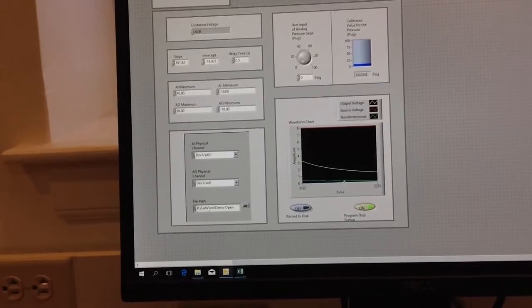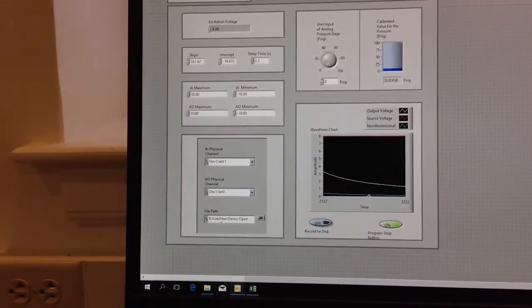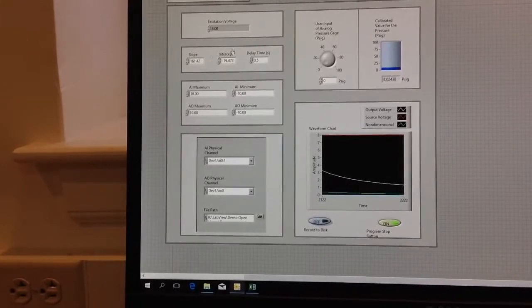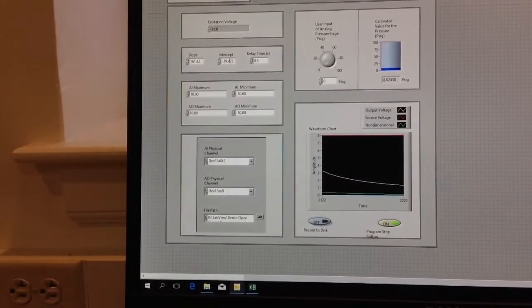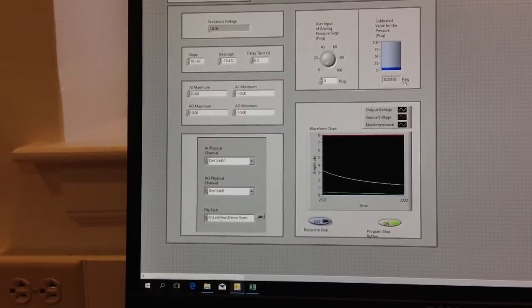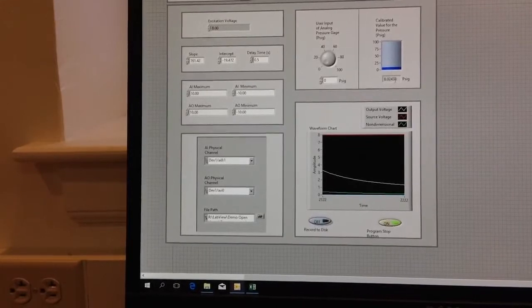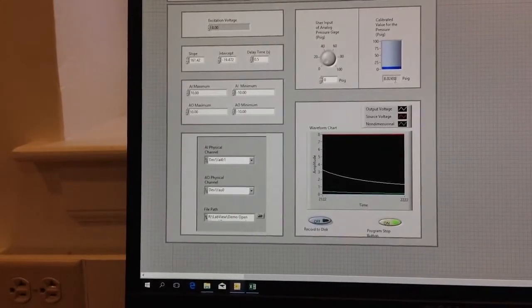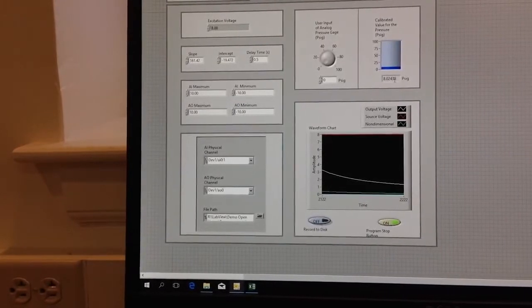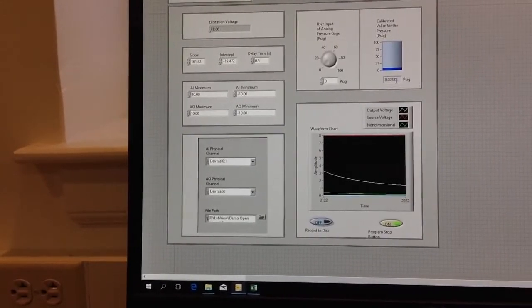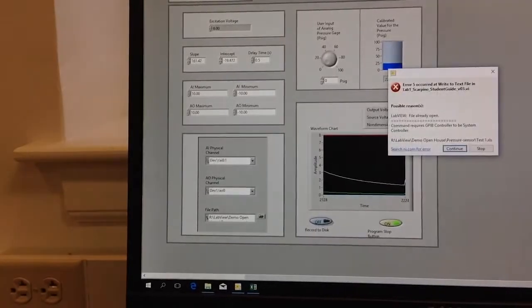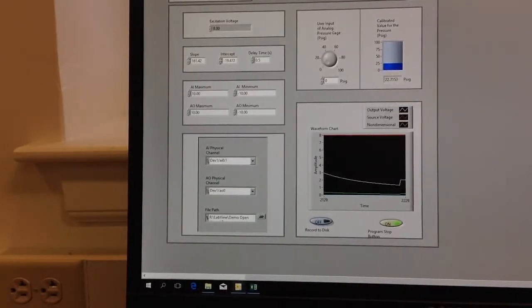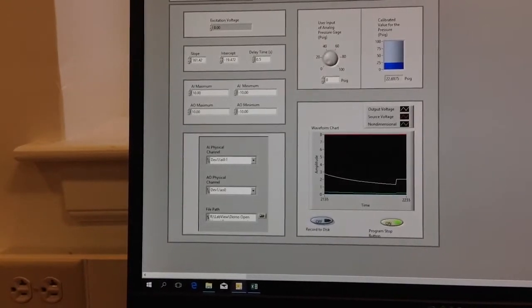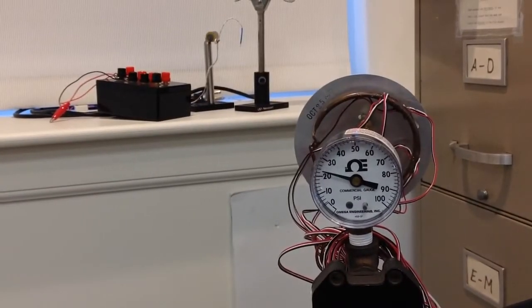So once you enter this into your program, so this is the LabVIEW program, a nice looking LabVIEW program. So I have excitation voltage and the slope that I got, and an intercept, and then I have some controls here, and finally I have the calibrated pressure here, okay? So now what I will do is I am going to increase the pressure, and let's see what this is going to read, okay? So I'm going to run the program. So right now it is getting 22 psi, and it is actually what's on the dial, okay?